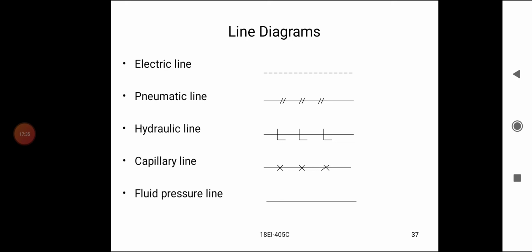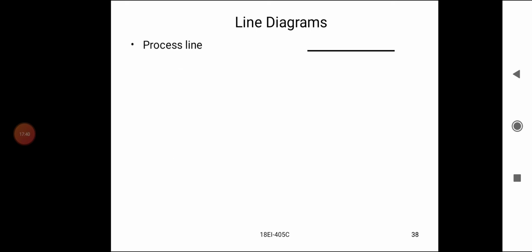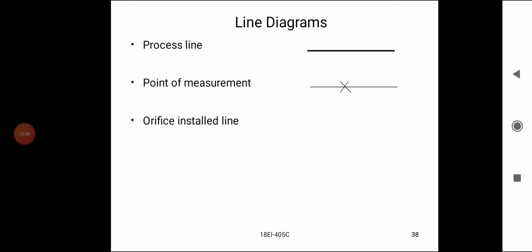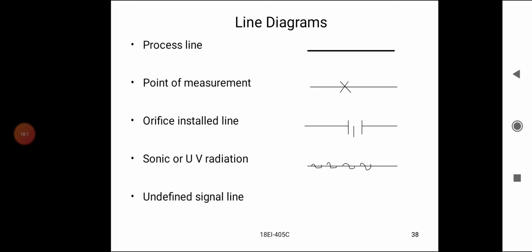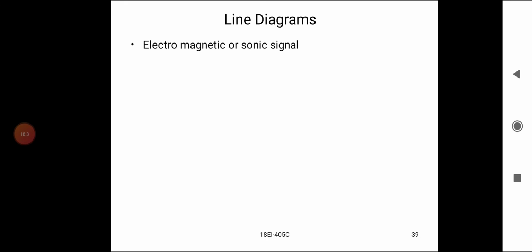The straight line: process line, thick straight line. Point of measurement, a straight line with a single cross marking which indicates a point of measurement. Orifice installed line, so an orifice meter is installed in the line. Sonic or ultraviolet radiation signal, a straight line with a sinusoidal signal. Undefined signal line, a straight line with single crossing lines on the straight line, which indicates an undefined signal line. Electromagnetic or sonic signal, so a sinusoidal line.